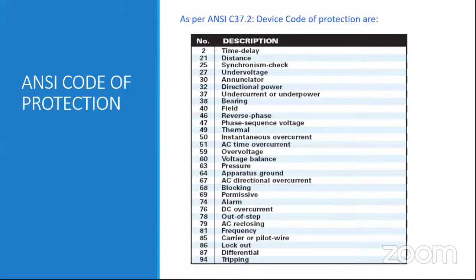50 is instantaneous overcurrent protection. This is for three phase short circuit fault protection. It should operate instantaneously if there is a fault; instantaneous overcurrent means primary protection. 51 is AC time overcurrent protection, that is, inverse time overcurrent protection, IDMT, which depends on time as well as the fault current. If the fault current increases, the time of operation will be lesser. As soon as the fault current rises, the time of operation will be minimum.